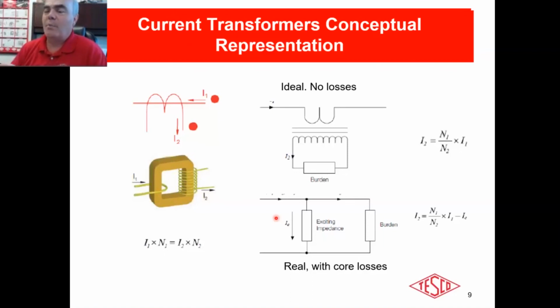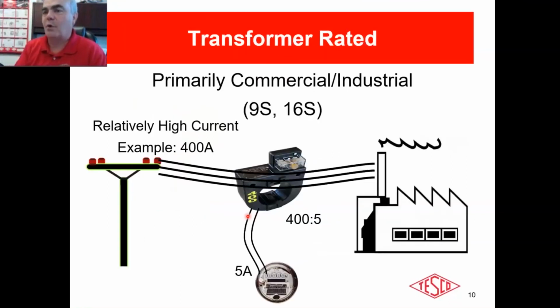So when we are billing our customer, we know that we're actually always billing them just less than 100% of the energy being delivered, all right, which is typically what our industry likes to do. Same thing with your meters. When you receive your meters, all of the meter manufacturers have traditionally calibrated up to 100%, which means the overwhelming majority of them come in at just under 100%. We always want to make sure that we are erring on the customer side instead of on the utility side. All right. So again, pretty simple. Primary, secondaries, that's your ratio. You do have a certain amount of loss there when you have a transformer.